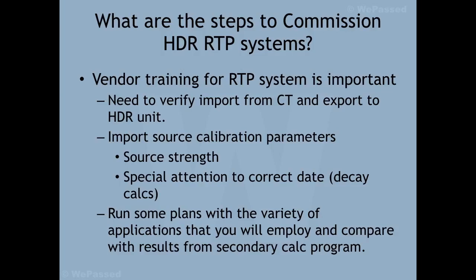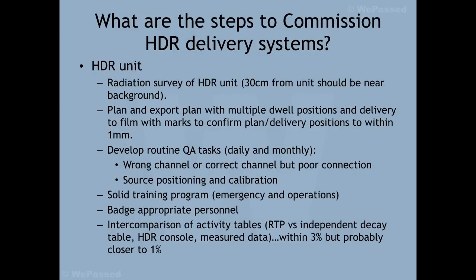For a new HDR machine, you have to do some surveys using survey meters that are valid and calibrated. First you survey around the HDR machine to see the exposure rate around it. Usually when you survey about 30 centimeters away from the HDR system, you get almost zero. If the reading is too high or not appropriate, you need to talk with the engineer from the manufacturer to make sure it's correct.